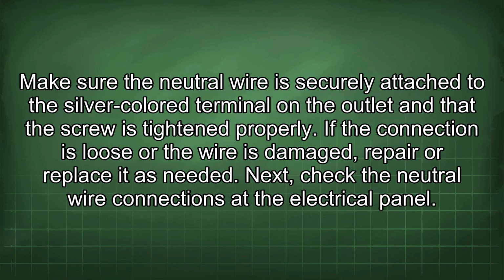The first step in troubleshooting an open neutral is to visually inspect the neutral wire connections at the outlet. Make sure the neutral wire is securely attached to the silver-colored terminal on the outlet and that the screw is tightened properly.